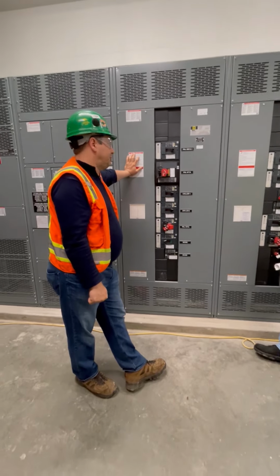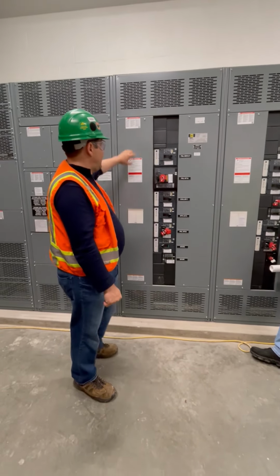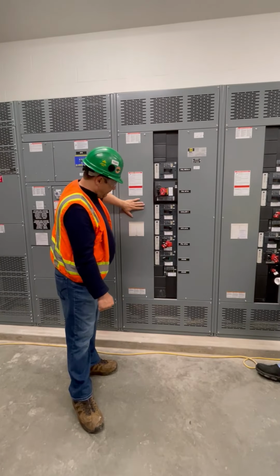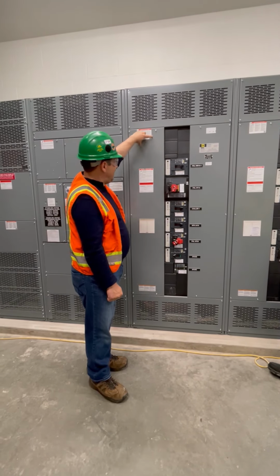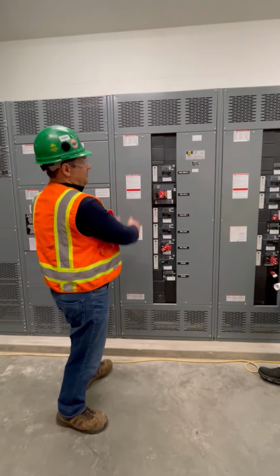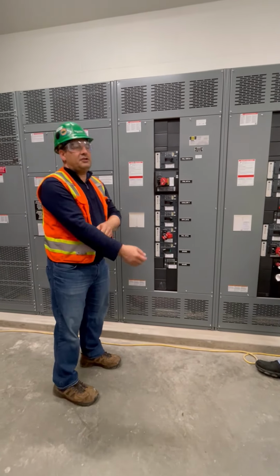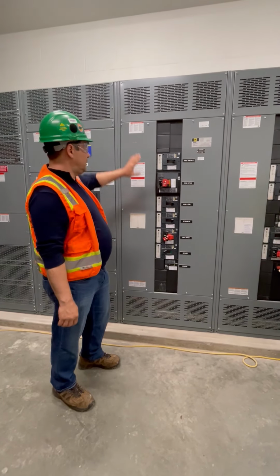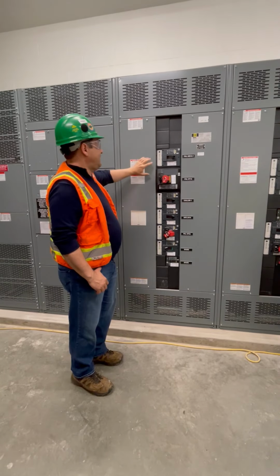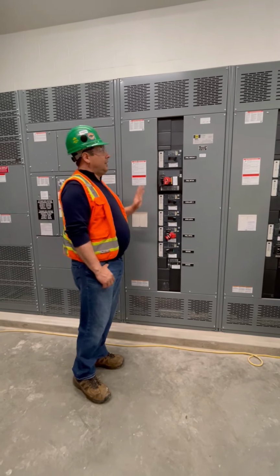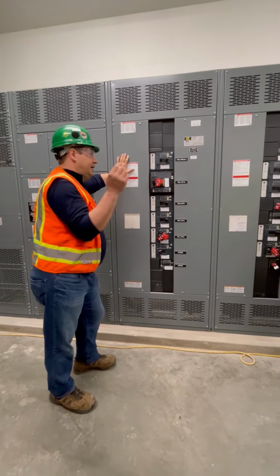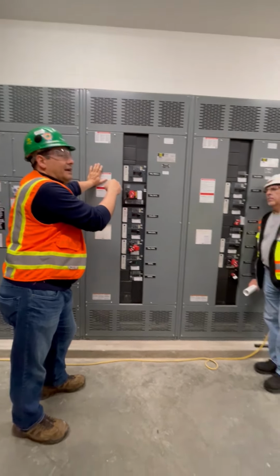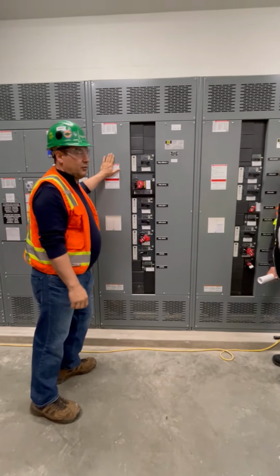A lot of customers will put in, in this particular case, IR windows. We replace this cover with a cover that has an embedded IR window from top to bottom. You can open it up, do your infrared, and check all the connections. Also thermal imaging. All on the cables, yes. Well, when I say cables, it's the connections to every breaker, right? The only thing you don't see is the connections in the back. So you can, if you put IR windows, right?